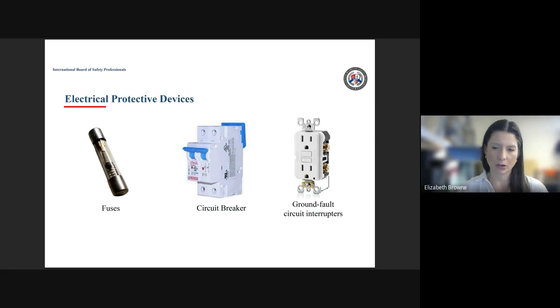Those can be put on at the individual outlets, and they also have ground fault circuit interrupters that are in line with the electrical extension cord. And then they also have ground fault circuit interrupters that can be applied to a circuit breaker, where it is on every item in that circuit. So, we commonly see these on the outlets, and you can see that they have a test and a reset button. So if it gets tripped, you have to hold the reset in, but you also can test it to ensure that it's working properly.